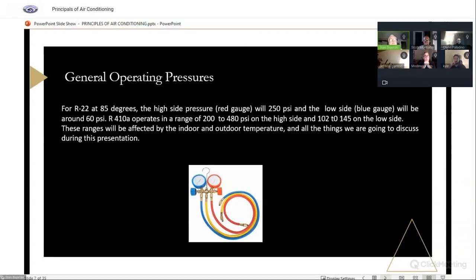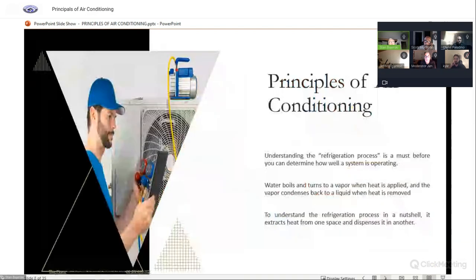Those ranges will be affected by the indoor temperature, outdoor temperature, and all the things that we're going to discuss during this presentation. So it doesn't tell them exactly what's wrong, but that's where they start seeing how this system is operating from within. So understanding the refrigeration process is a must before you determine how well a system is operating.